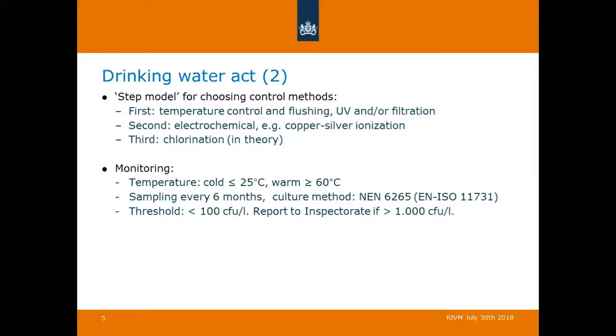You also have to monitor your control methods. If you use the temperature control and flushing method, you have to check your temperature: the cold water needs to be 25 degrees or lower, and the warm water needs to be 60 degrees or higher. You have to take culture samples every 6 months, and you have to sample the taps that are most distant from the water meter or most distant from the boiler, or taps that are not used very often.